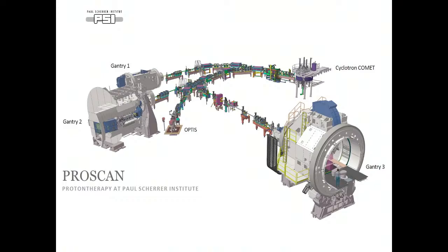And I want to mention one point here. The cyclotron, as you know, gives a fixed energy, but for the clinical application, you need a range of energy. And so you must reduce the energy from the 250 to whatever you need. We go down to 70 MeV clinically.